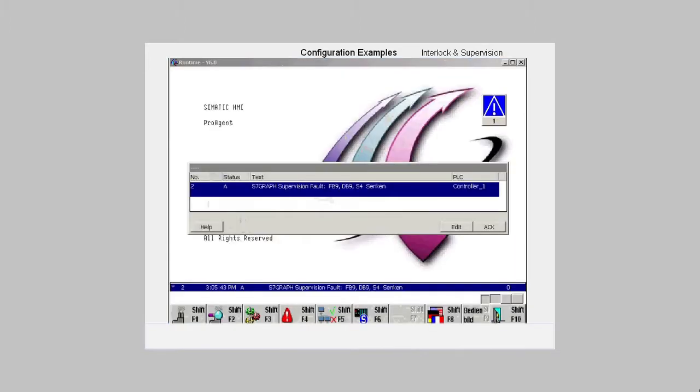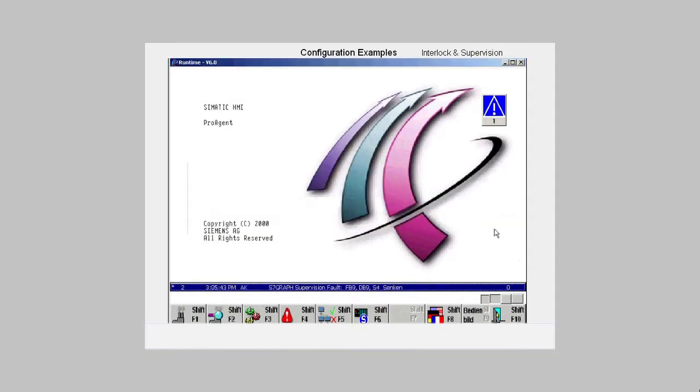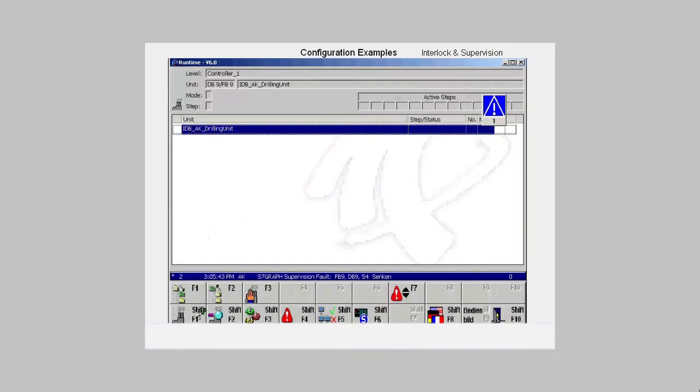Once a process fault has been triggered, for which the supervision has been configured, in other words the lower step was not completed within the time limit set, the supervision fault is announced in a message window. We acknowledge the message and switch to the overview in which we can see at which level and in which unit the fault has occurred.